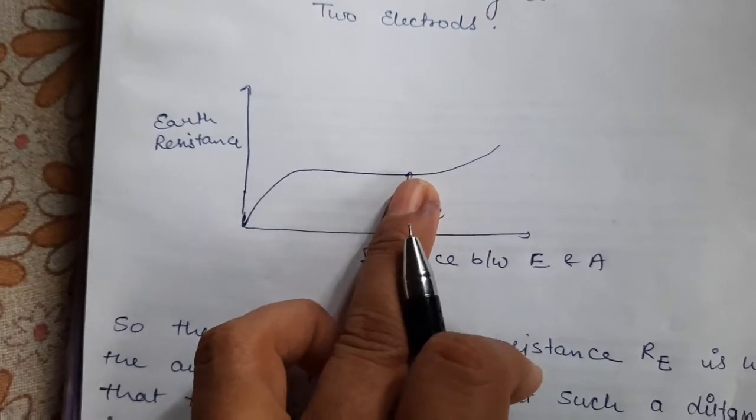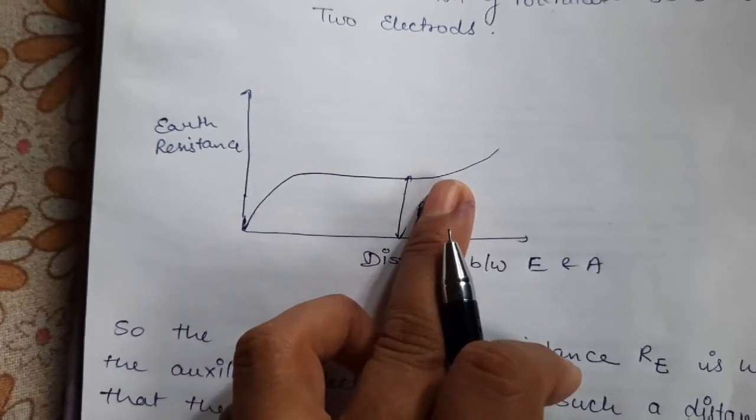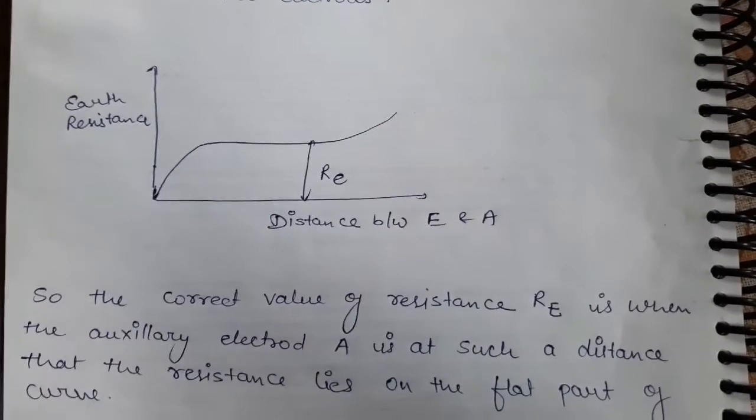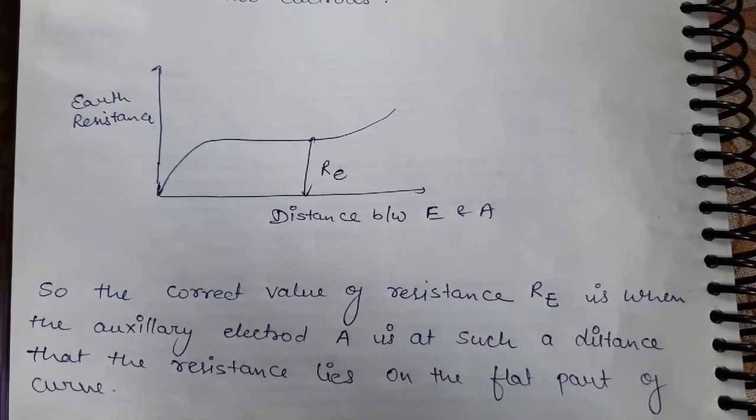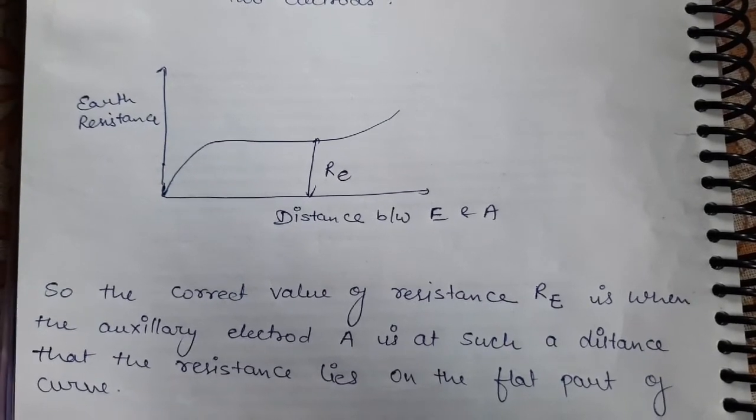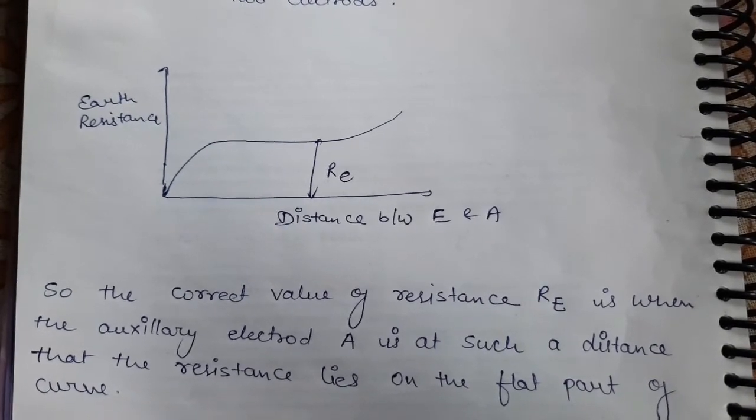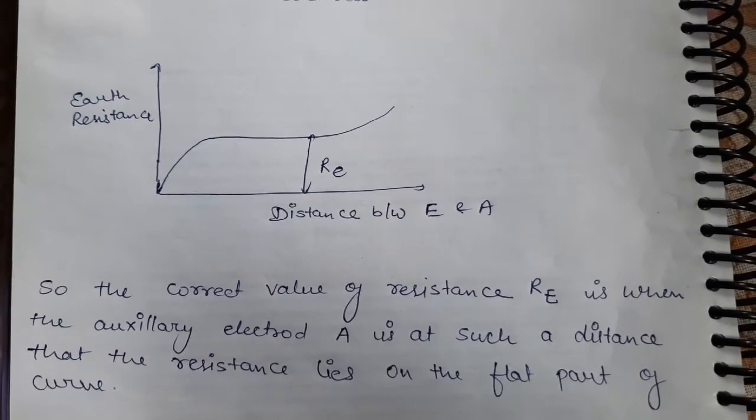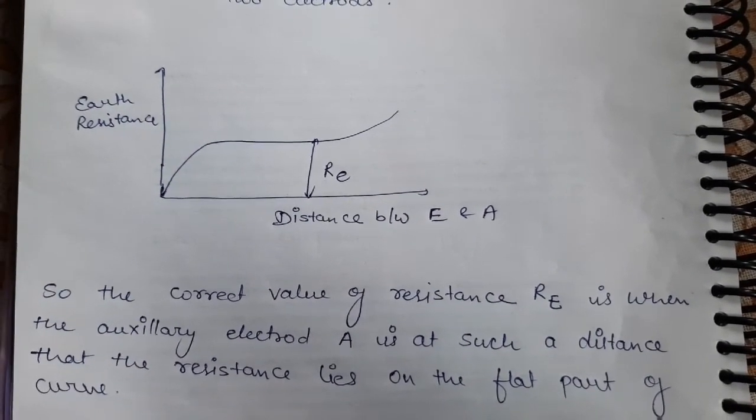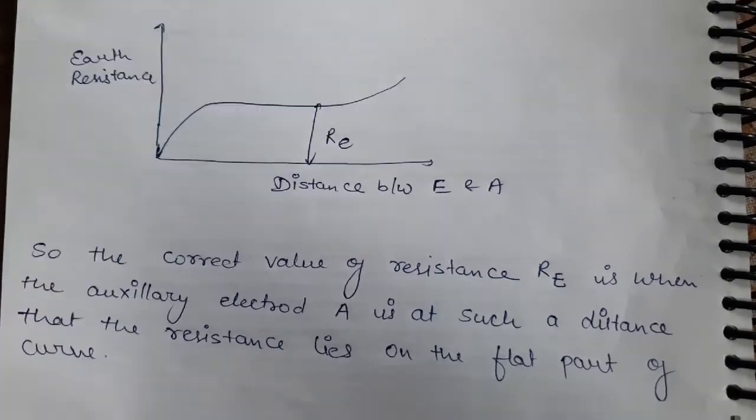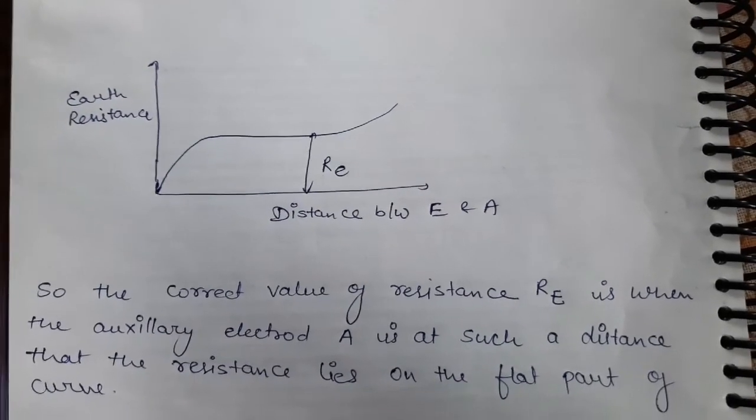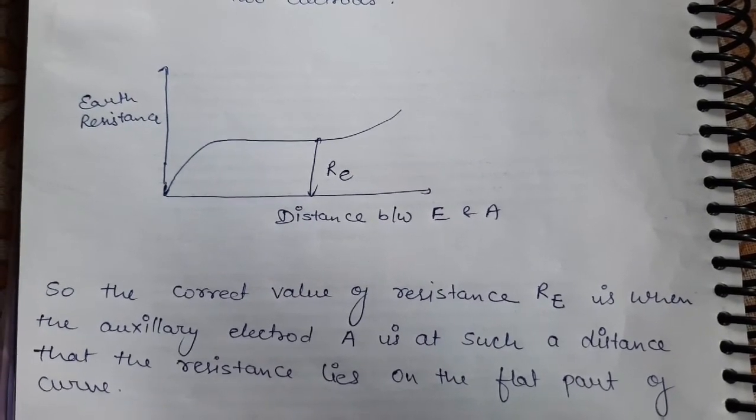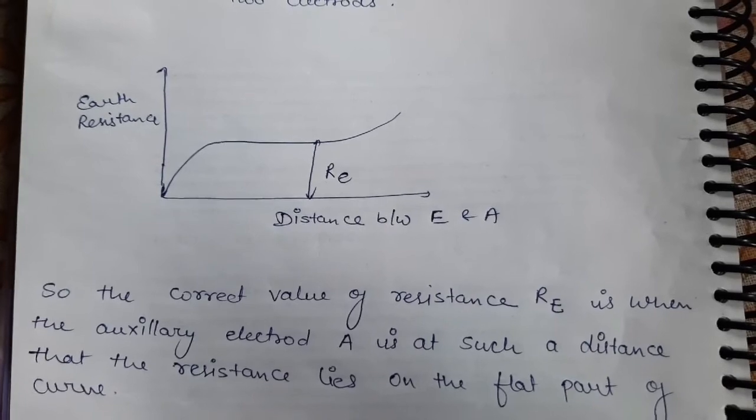The correct placing of the auxiliary electrode is important. If placing is not correct, there will be an error in this method. The correct value of resistance RE is when auxiliary electrode A is at such a distance that the resistance lies on the flat part of the curve. Near the auxiliary electrode or earth electrode, error will be produced. In the middle part, the earth resistance will be accurate.